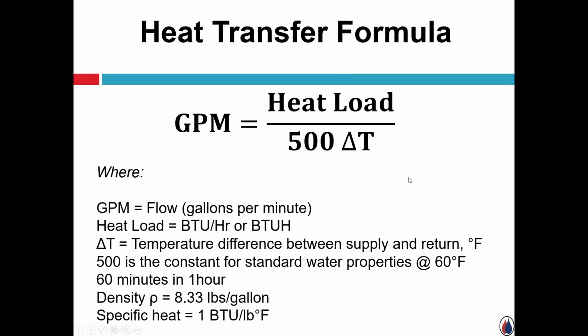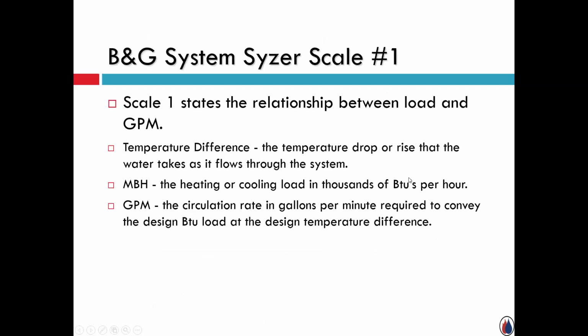So moving forward, that's the formula behind the scenes. You can work it frontwards and backwards, but in this case we're saying gallons per minute equals the load divided by 500. We talked about it last week: typically it's 60 degree Fahrenheit water, so it has a weight of approximately 8.33 pounds per gallon. The flow rate is described in gallons per minute, and the load is typically in BTUs per hour. So we're taking that weight, 8.33 or 8.34, times 60. When you do the math, it's 500 times your delta T, your change in temperature. So that's the formula. You don't need a wheel. You can just sit there and plug in, but the wheel is a very convenient way of doing it.